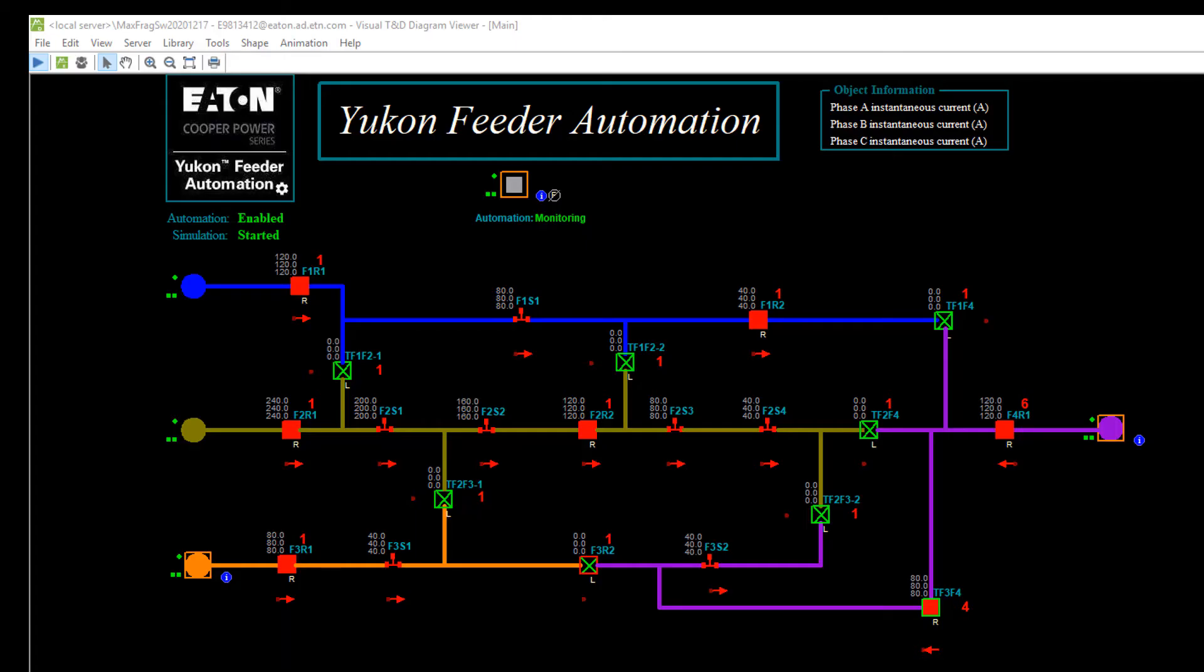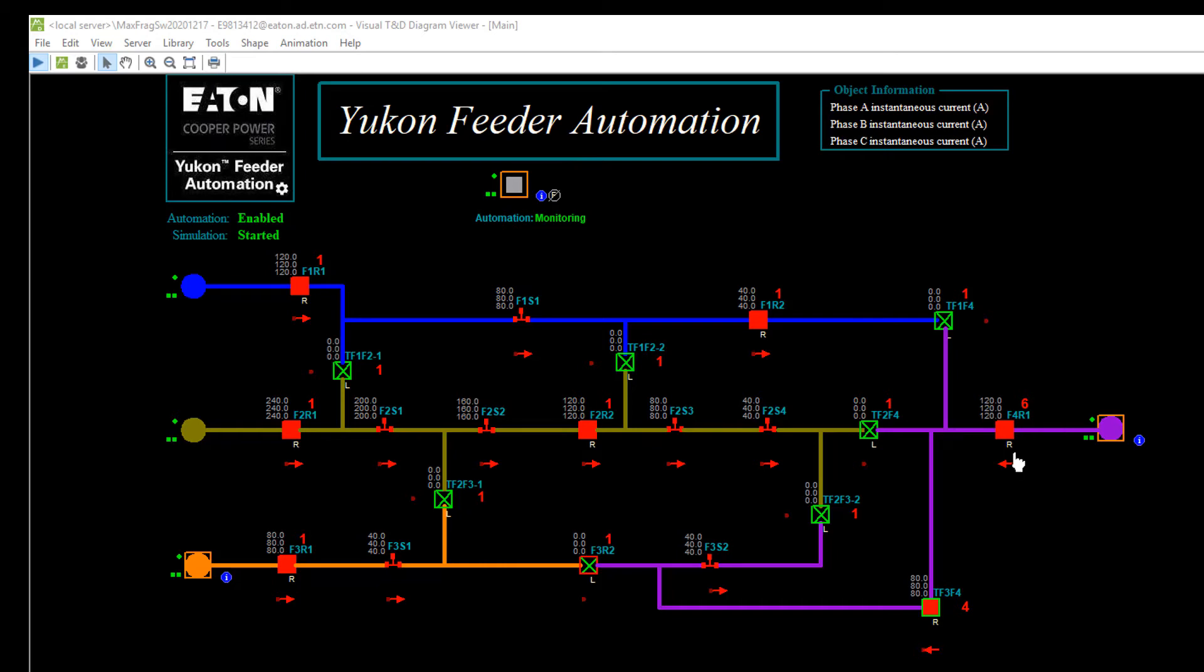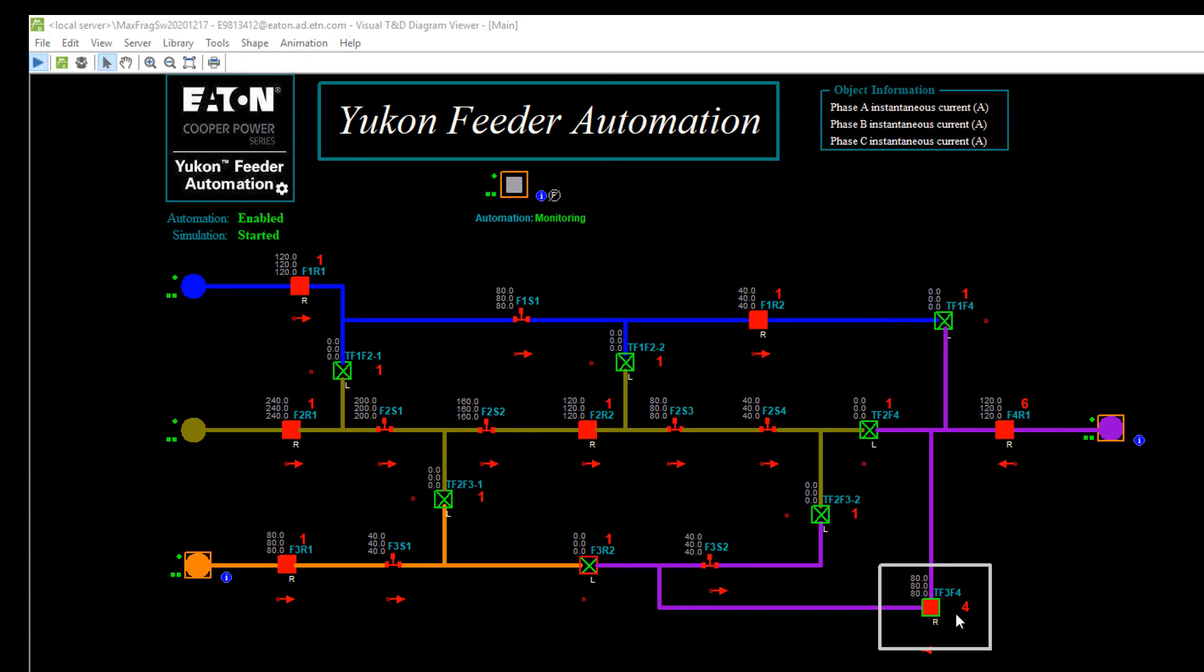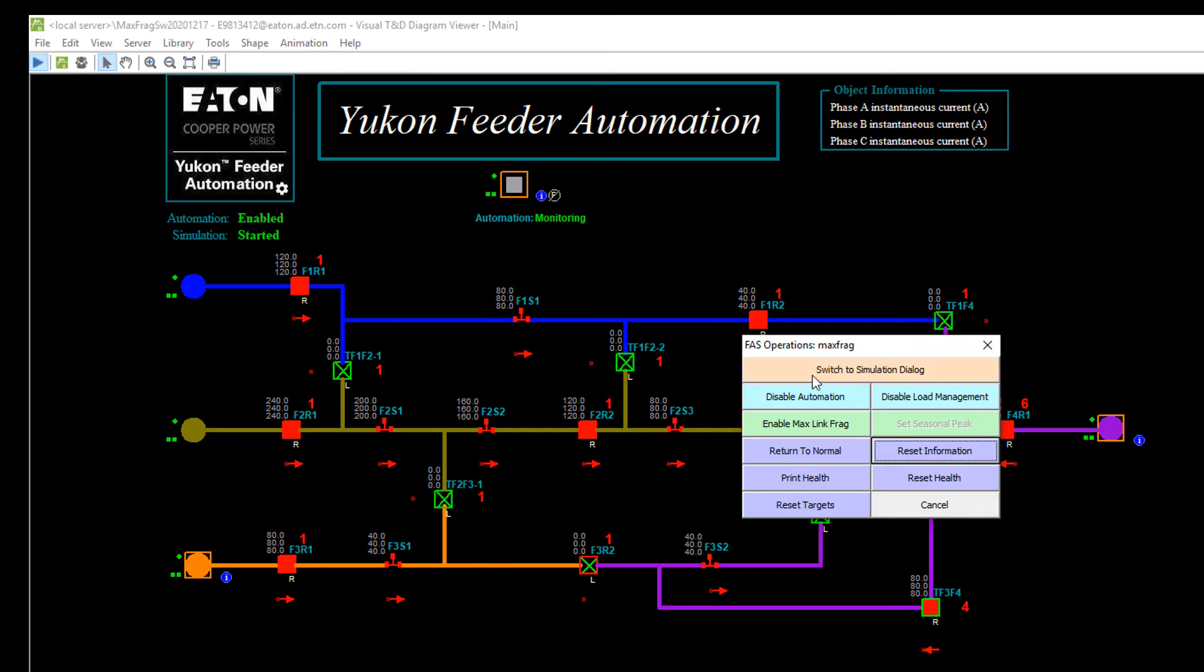Switching back to my diagram, I can now come into this system and let's do return to normal. Now as I do return to normal, I expect this device to switch its profile back to profile one. However, this device, it won't be fed off of any particular source, so let's see what happens with it.